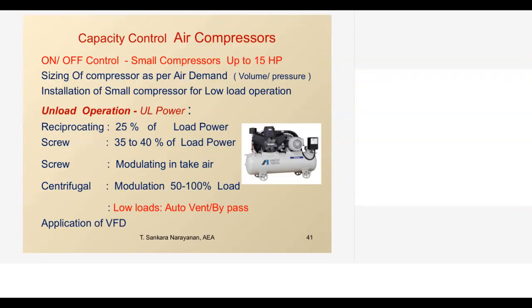So the other utility is the air compressor. In air compressors, again we are having capacity control. One is on-off control. Whenever air is required, we can switch on the compressor. This is possible only for smaller compressors up to 15 HP or 20 HP. Beyond that, if we are putting a higher rating motor, the motor is having certain conditions. I can't start and stop the motor continuously in an hour. So there are certain guidelines on how to control the compressor capacity.